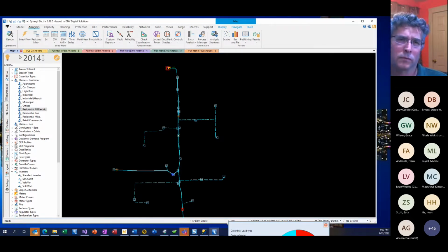Then we start load flow. Load flow opens that file, starts at January midnight, grabs all the loads, assigns them to the model, runs load flow, and goes to the next hour. That's why the performance is good. If you're running Oracle SQL Server, then this should run pretty quick for you, and certainly once the data is out of the database, it runs fast.